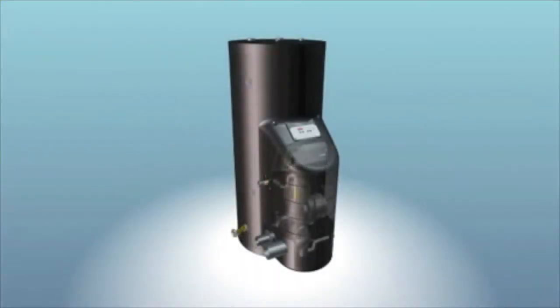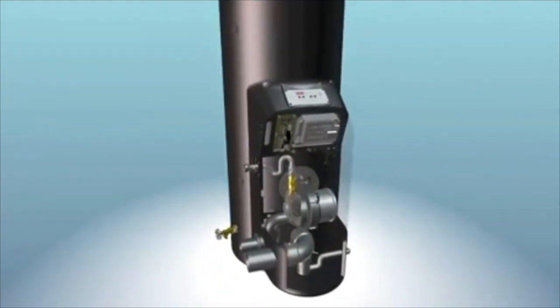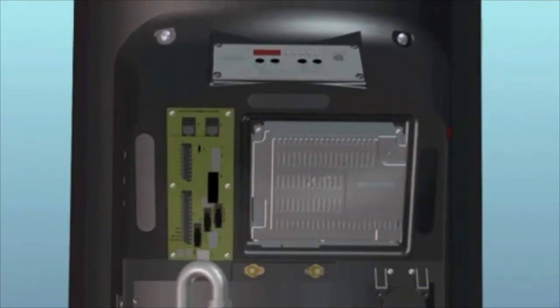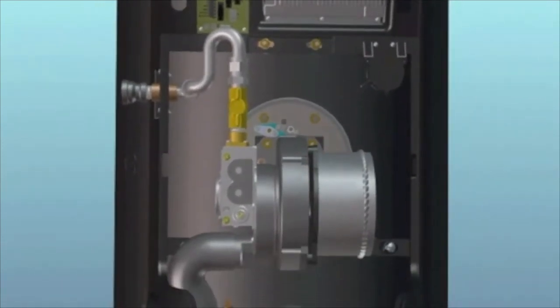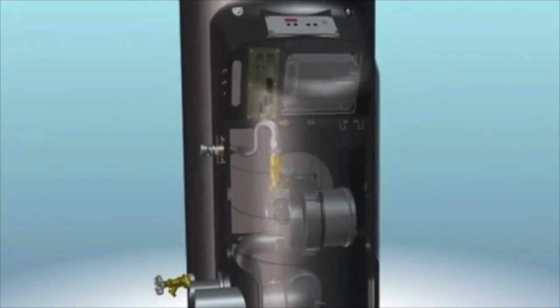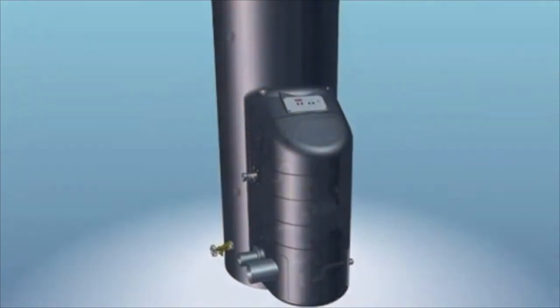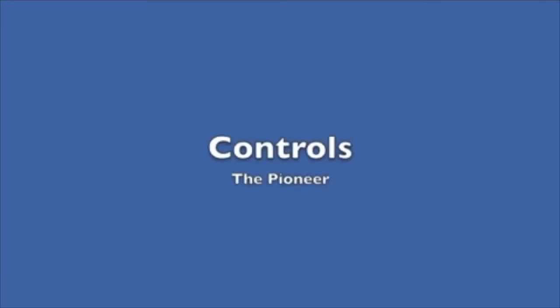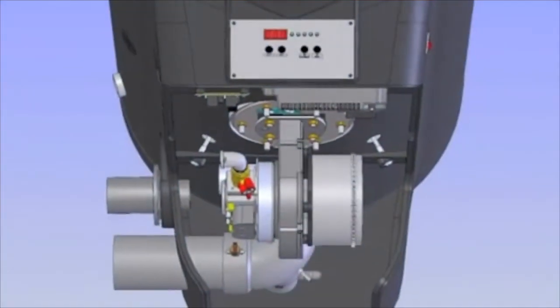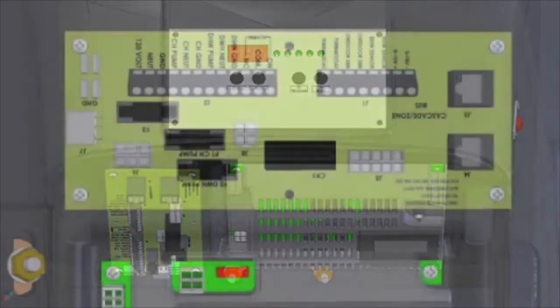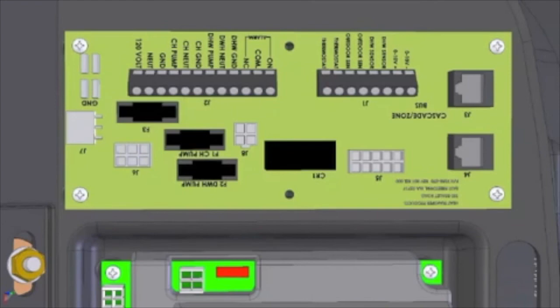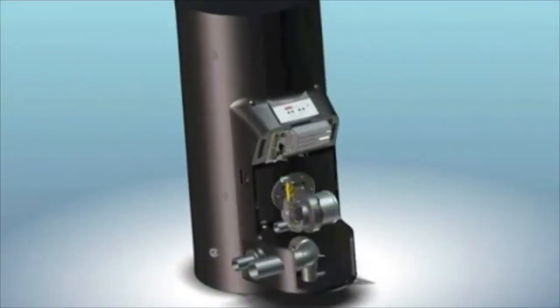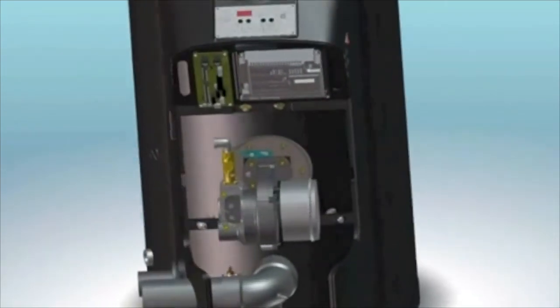Pioneer controls and combustion system use many of the same parts already being utilized in other HTP boilers. This commonality allows our customers to be able to minimize replacement parts and unnecessary training for this appliance. Controls. The Pioneer uses HTP's reliable 926 board, which has a state-of-the-art PI controller. With standard features such as outdoor air reset and cascading capabilities, the Pioneer can achieve the same high system efficiency as leading low-mass condensing boilers.